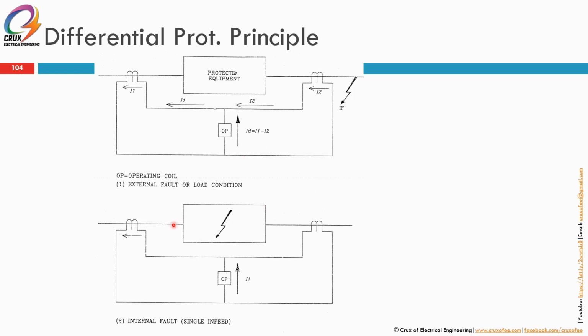But if the fault happens within the transformer, at the cable termination, anywhere along the cable between these two CTs, the second CT, CT2, will not measure anything. Kalau masa ni ada load current, dia akan measure the normal load current saja. But this CT1 will measure not only the load current but also the fault current. So because the fault current is only at one side, the operating coil, ID equals I1 minus I2, I2 is equal to 0, so you get ID equals I1. So if I1 is above your I differential setting, the operating coil will operate and trip your breaker, both upstream and downstream at the same time, very fast, 40 to 50 millisecond.